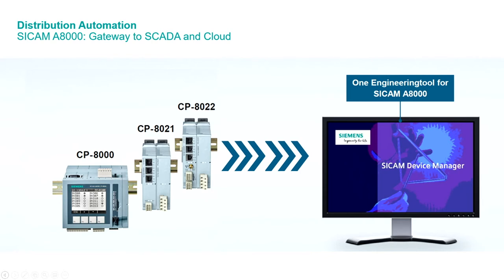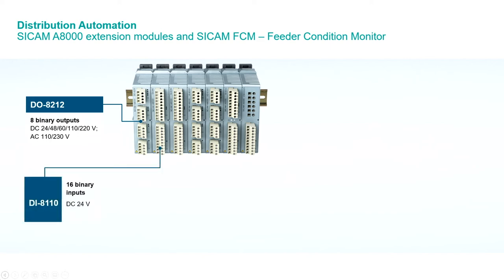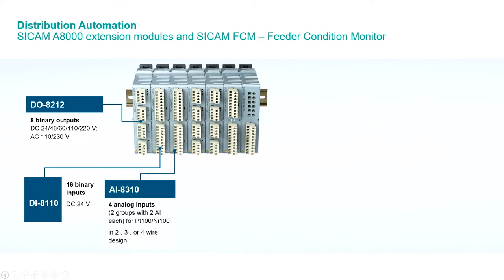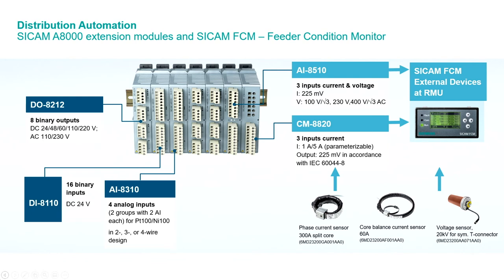The SICAM A8000 CPUs can be extended by various extension modules perfectly tailored for the secondary substation. We have different digital output cards like the DO-8212, or digital input cards like the DI-8110, which are perfect for controlling load breakers and station signals. In addition, we have an I/O card perfectly tailored for PT100 sensors to get temperature from the station or from the transformer. We also have cards which implement SICAM FCM functionality. The SICAM FCM is the Feeder Condition Monitoring system, able to control and monitor each feeder to get fault indication, currents, voltages, and all relevant data of a feeder in a medium voltage bay.